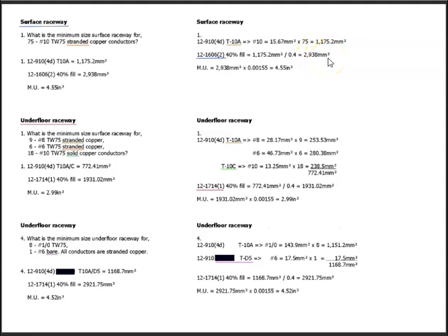So what we're doing here is actually sort of creating the table 9s. Table 9G is what we've been using typically, so this is already pre-calculated in table 9G for us. What we're doing is solving for that part of the calculation. So here the surface raceway must be at least 2,938 millimeters squared.